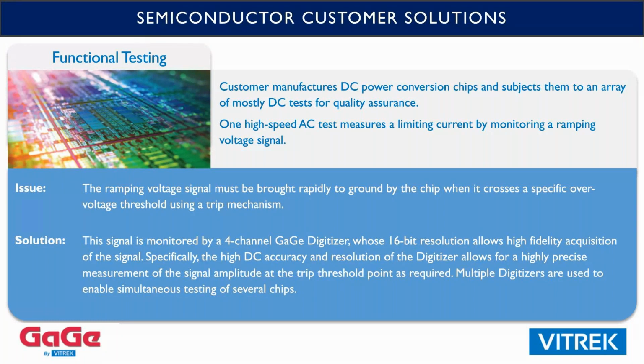So they have one particular test on their power chips that requires the chip to trip at a certain limiting current. So, at relatively high speed, they ramp up the current, and then basically the line should open once the current exceeds a certain very precise value, which of course they turn into a voltage to measure with our card. So they use one or more of our 4-channel cards so that they can probe 4 chips in parallel testing. They have an elaborate chip mounting system that gets the chip into the jig, and they can do 4 or 8 at a time.